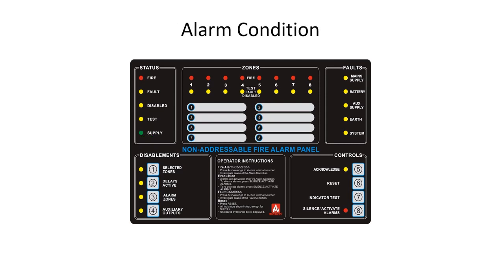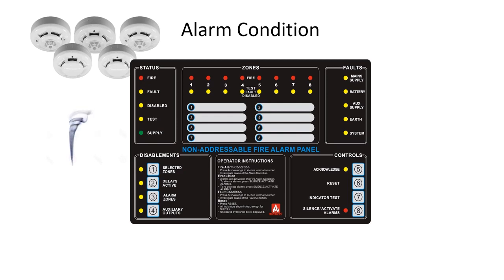In the alarm condition, the panel has received a fire signal from a detector or a manual call point. The fire indicator, the relevant detection zone indicator, and the acknowledge indicator will flash. At the same time, the internal sounder will operate, and the silence activate alarms indicator will also be on.